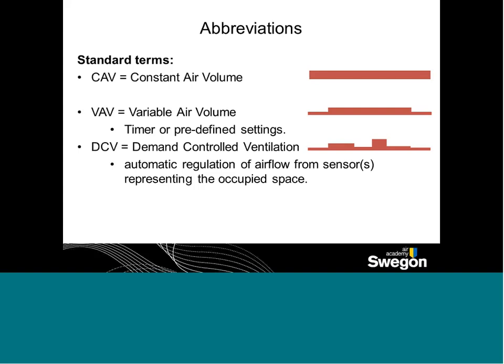This means you need room sensors that give a measurement of the IAQ or temperature in the room, and this needs to be used to control the airflow according to the desired IAQ. That means you need to specify in a qualitative way the objectives the DCV system is hoping to fulfill.